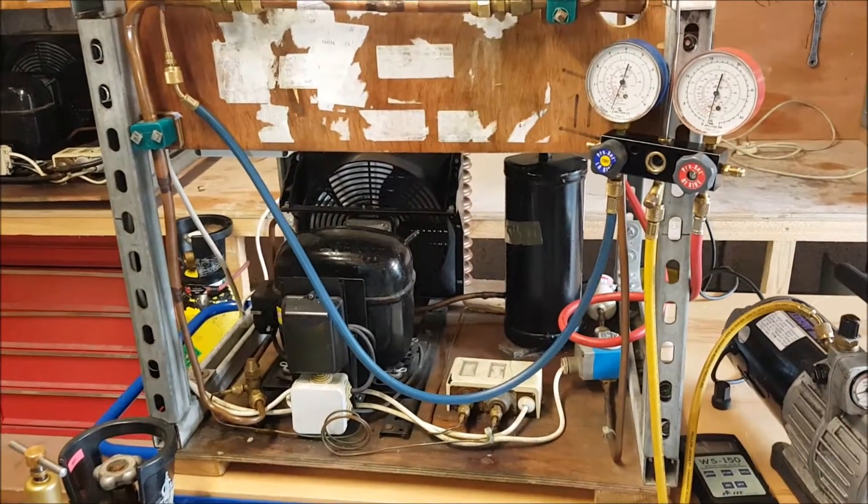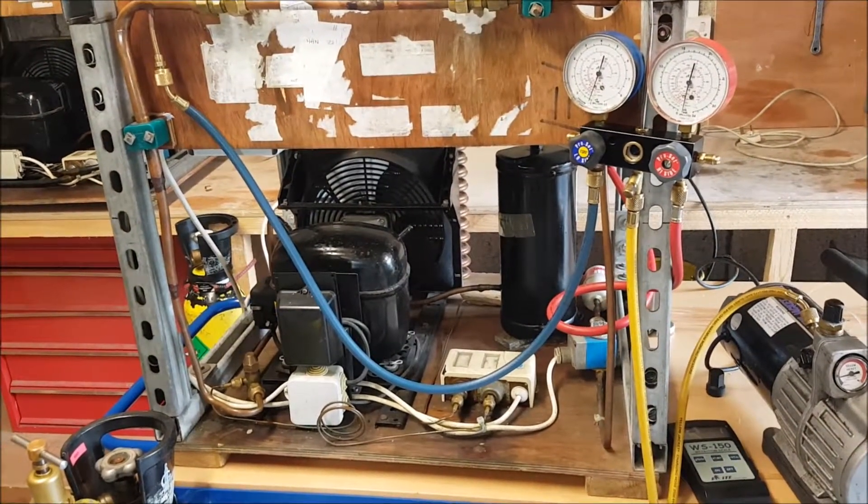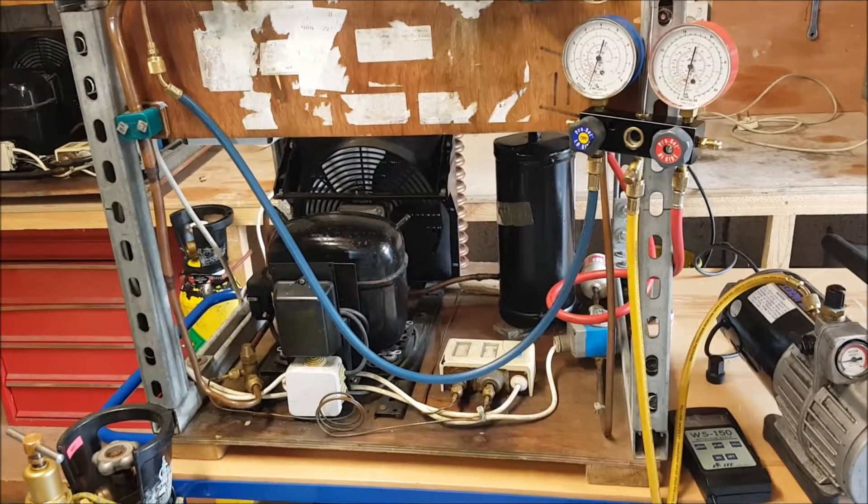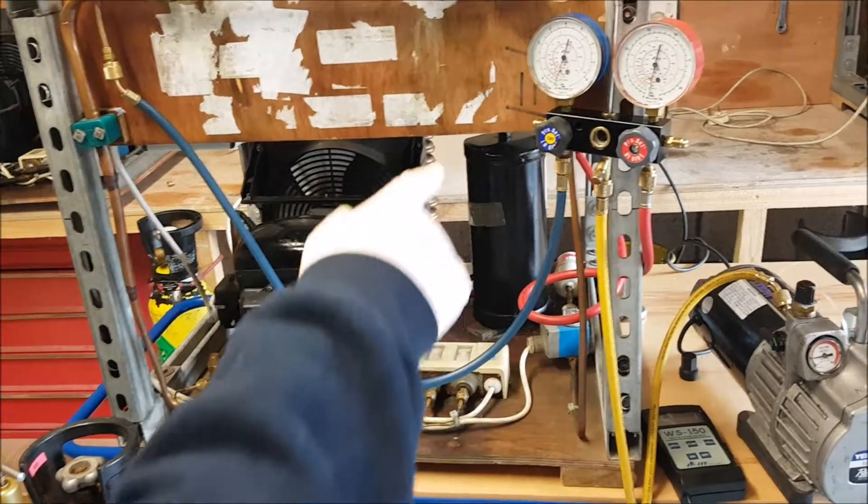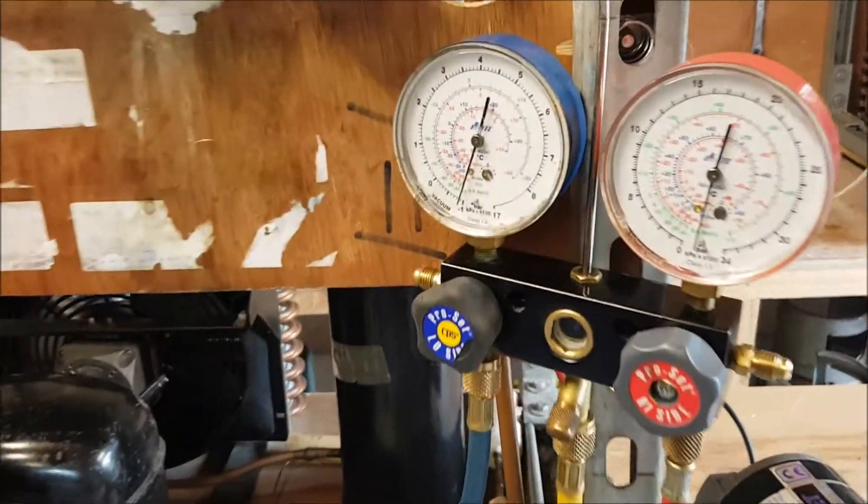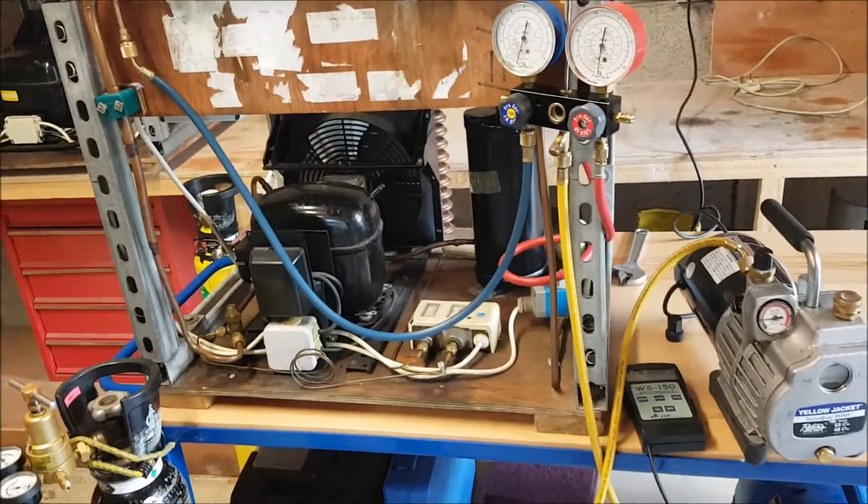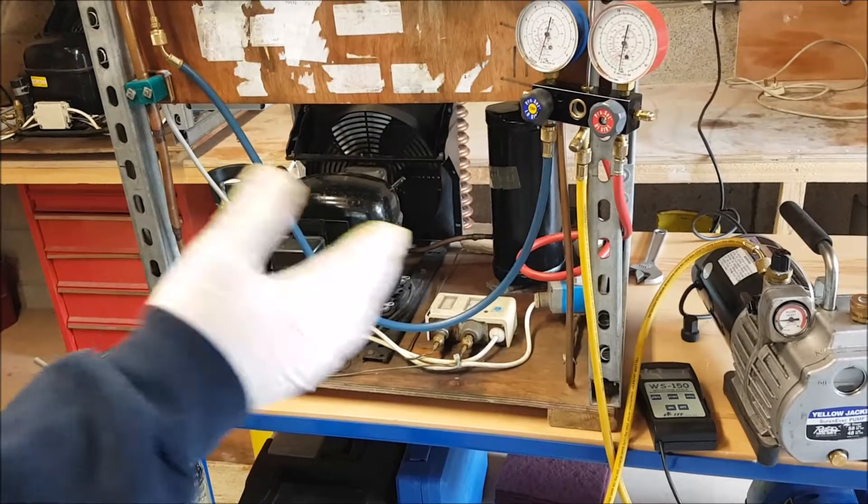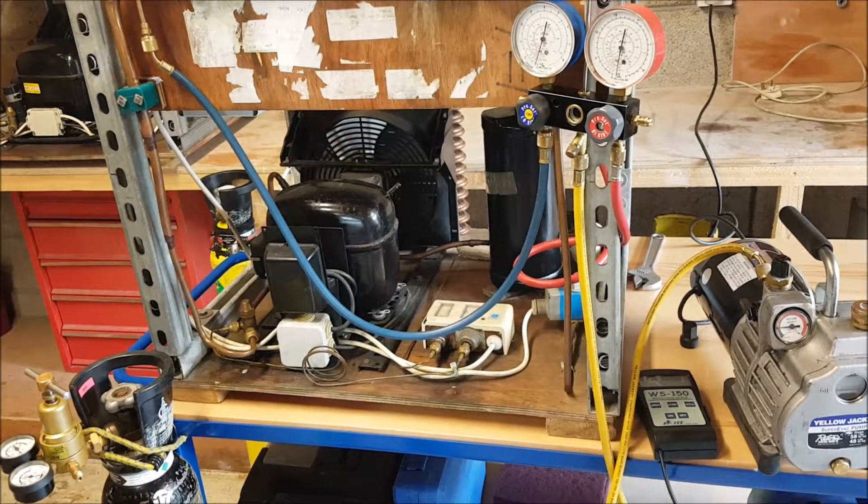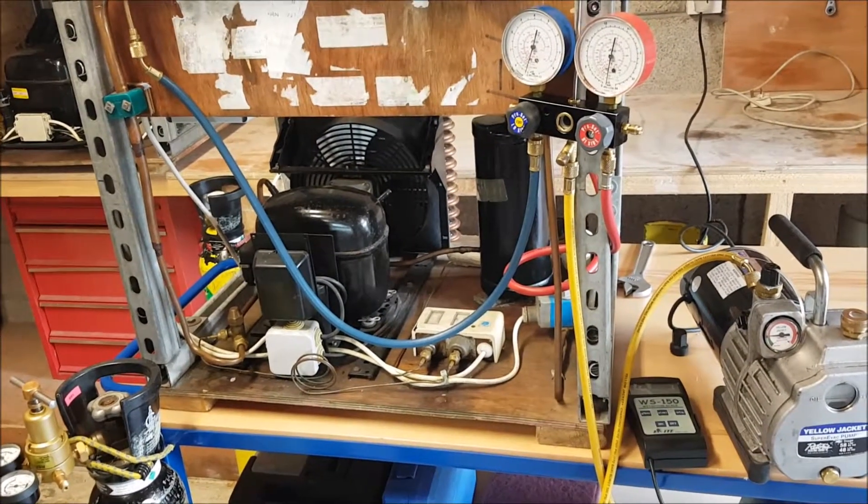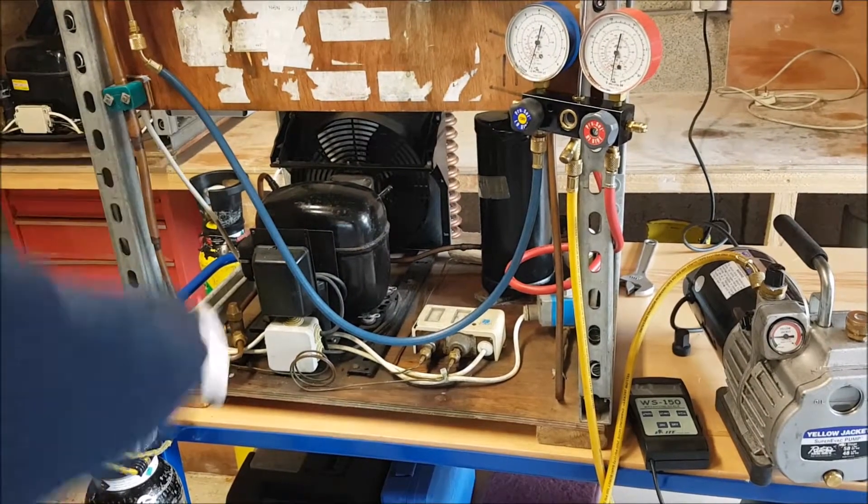Okay, welcome back to refrigeration training with 3D Interactive Learning Technologies. We have now achieved our vacuum. From last week you saw where we did our vacuum pump. We've removed our torr gauge because we didn't want to put any positive pressure onto it. We've refitted our low-side service gauge.